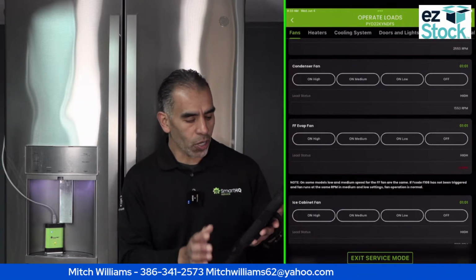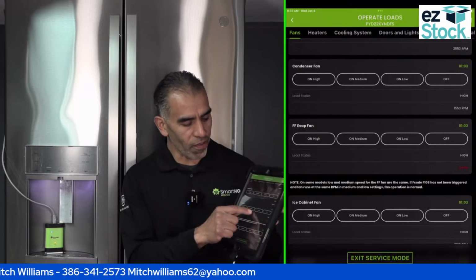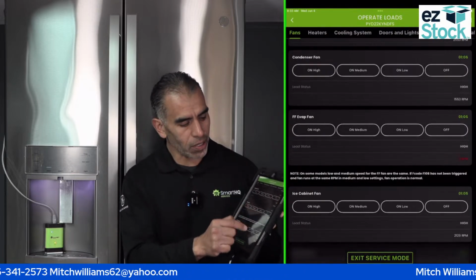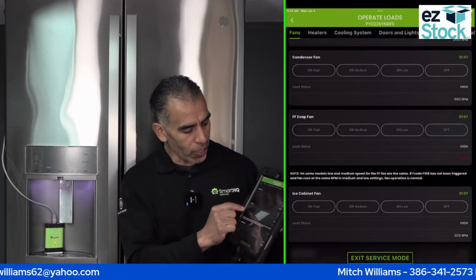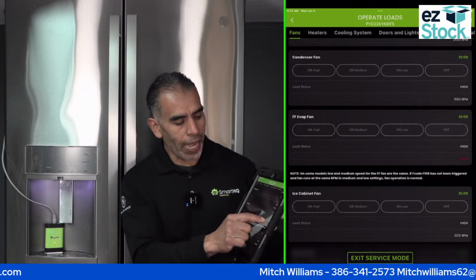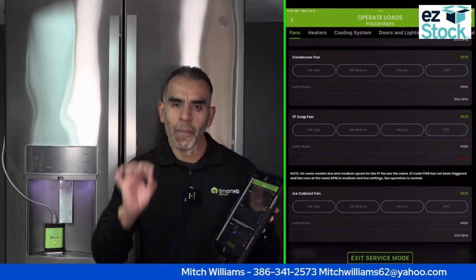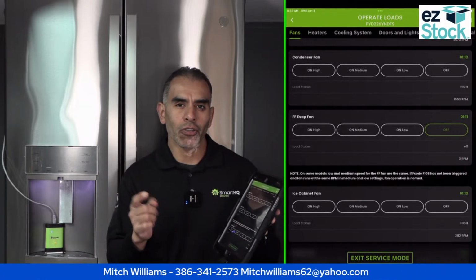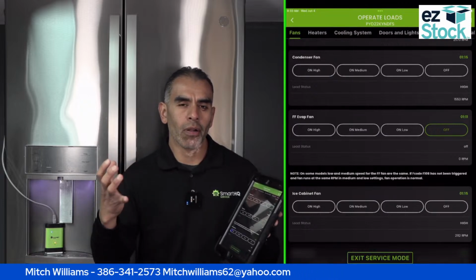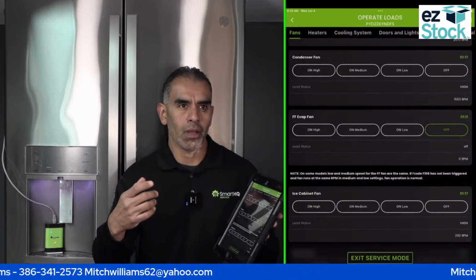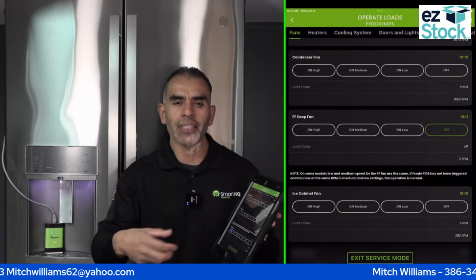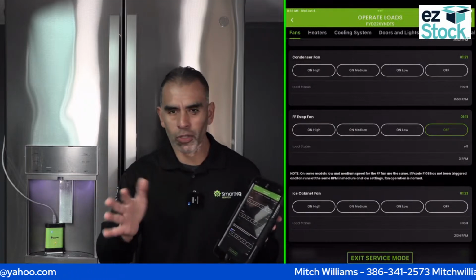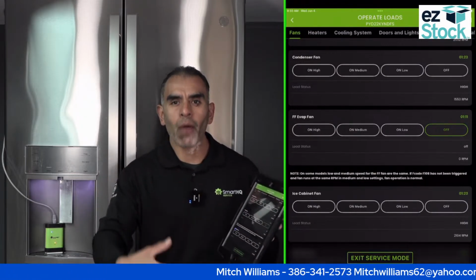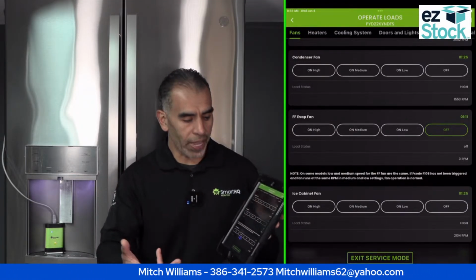Let's shut off the fresh food evaporator fan. Watch closely where the red is. We'll turn it off, and you'll notice the load status goes from high to off. That's your main board, right? You sent the command signal to the main board to shut off the function that sends power to the fan.